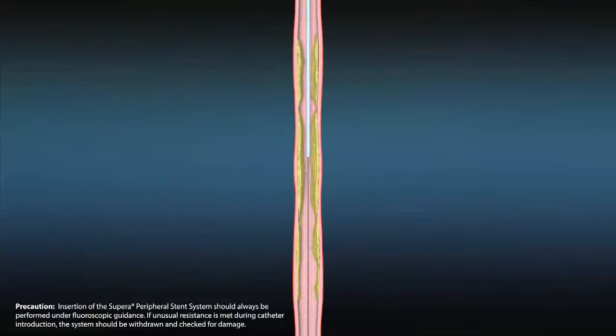Prior to use, Supera should be removed from its packaging, inspected for bends or kinks, flushed and wiped prior to use per the instructions for use. The Supera catheter should be introduced into the sheath utilizing an 014 or 018 guide wire. Advance the system until the distal sheath marker and the stent length marker encompass the target lesion.